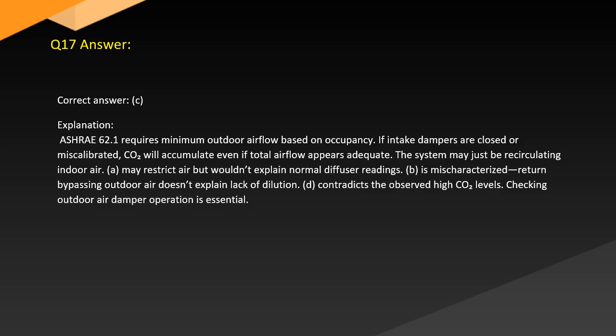Answer. Correct answer: C. Explanation. ASHRAE 62.1 requires minimum outdoor airflow based on occupancy. If intake dampers are closed or miscalibrated, CO2 will accumulate even if total airflow appears adequate. The system may just be recirculating indoor air. A: it may restrict air but wouldn't explain normal diffuser readings. B is mischaracterized. Return bypassing outdoor air doesn't explain lack of dilution. D: contradicts the observed high CO2 levels. Checking outdoor air damper operation is essential.